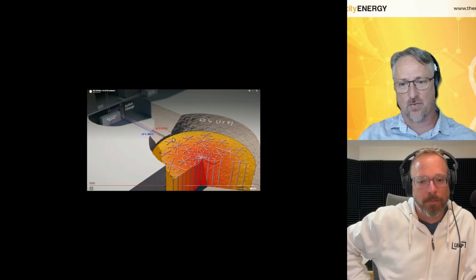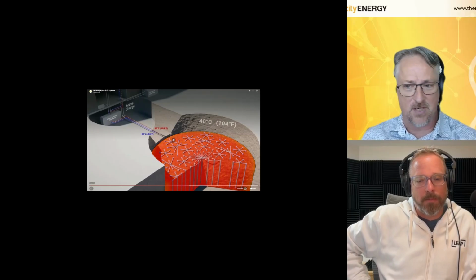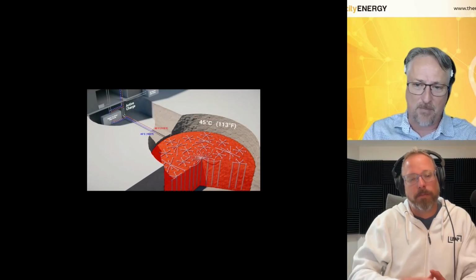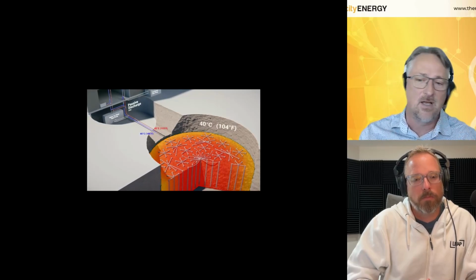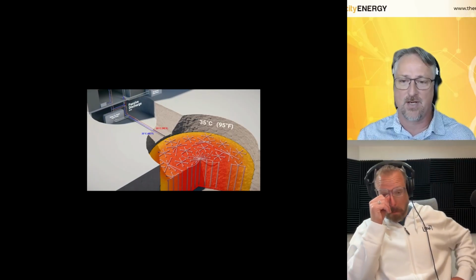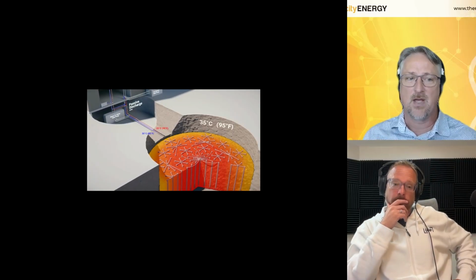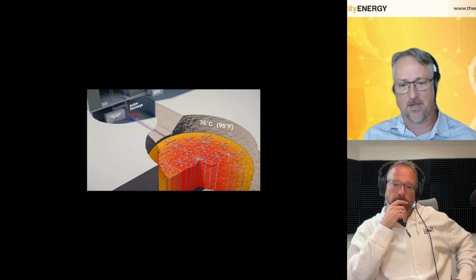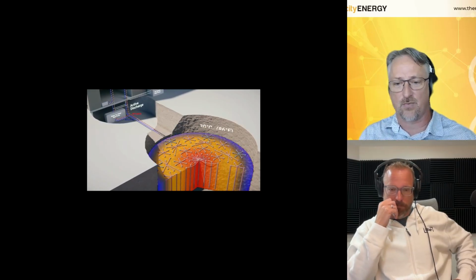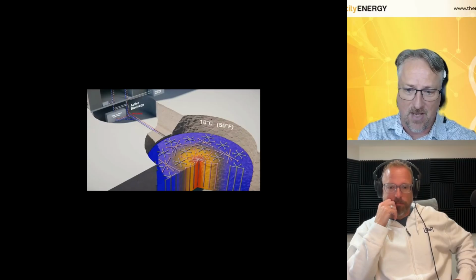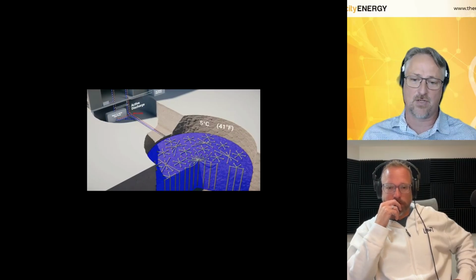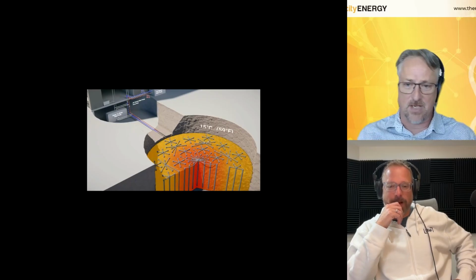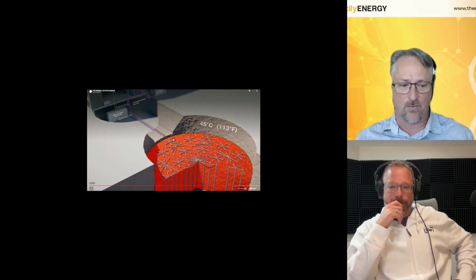So actively, we charge from 20 Celsius all the way up to 45, 50 Celsius if we need it. This is kind of our optimal 45 Celsius. Now, at the beginning of the season, 45 Celsius is enough to heat your buildings. So we passively discharge. We just run a circulation pump, and it takes the heat out of the field until it gets too cold outside and we have to have more than 35 Celsius to heat the building. So then we'll turn it into active mode on the heat pump, and it'll suck the heat out just like a Geoexchange field would, but it sucks it from the outside in. And we save that stored heat at the core for that peak of the winter to make it through that. And then the year cycle is completed. We've done a full year cycle.